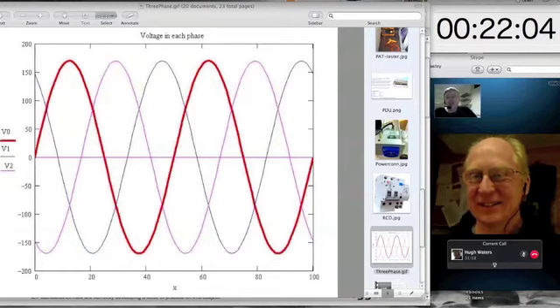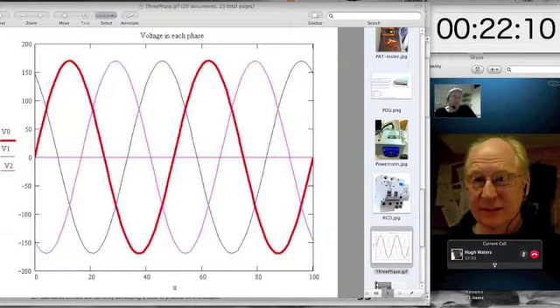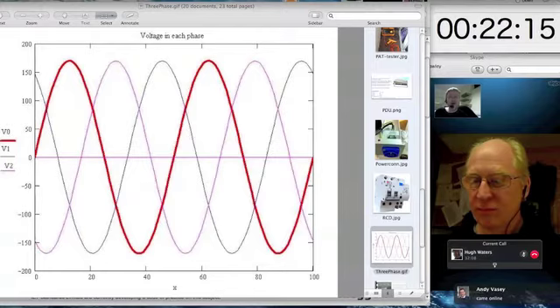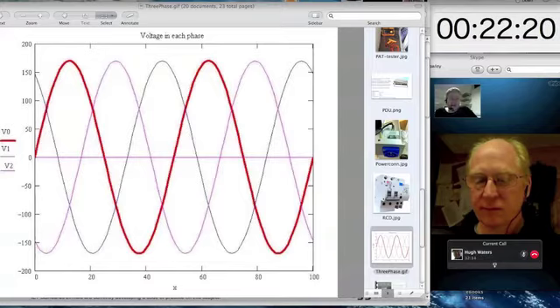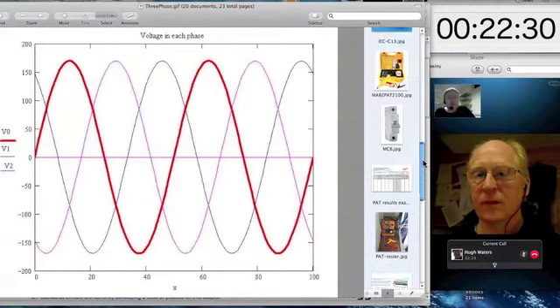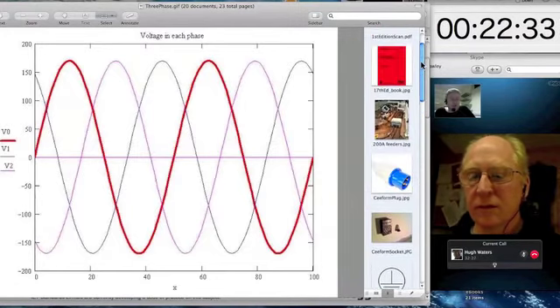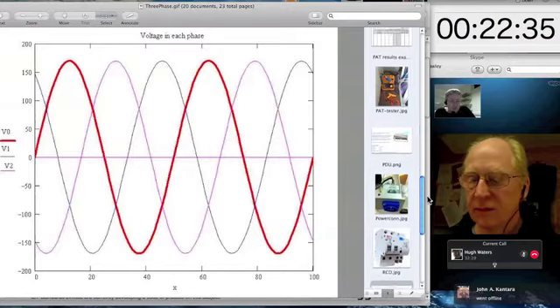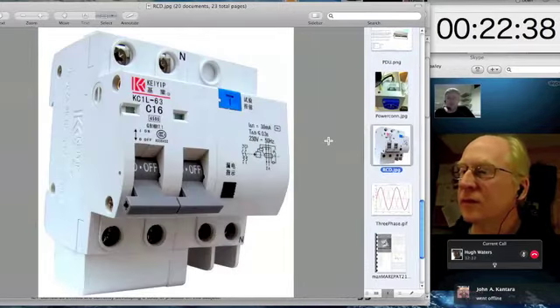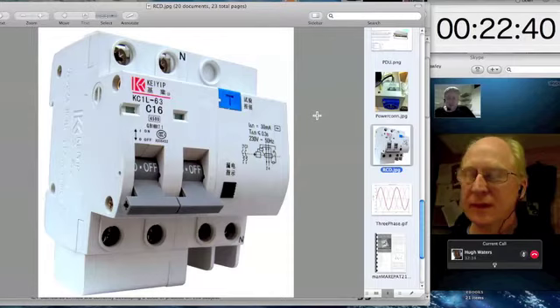Yes. But it's expensive. If you're obliged to run that machine room on one phase, that may well represent 90% of the current that your facility's pulling. Yeah. And in fact, over the last 10, 15 years, the regulation has been relaxed to allow you to do that. And in fact, now you go in most machine rooms, you go in most comms rooms, and you see the bays run red, blue, yellow, red, blue, yellow. And in fact, they intentionally put them on different phases. Now, one of the reasons why that's now an acceptable way to carry on, and I'm just popping up a picture now of a residual current detector, an RCD, is for precisely these gadgets.